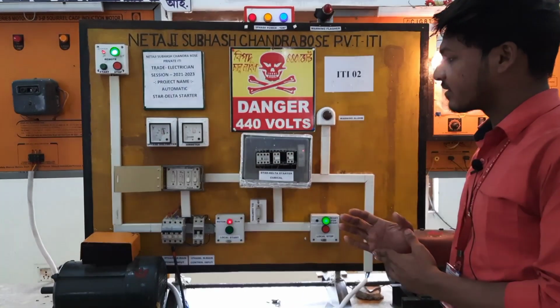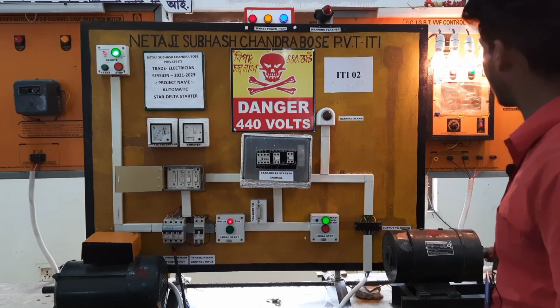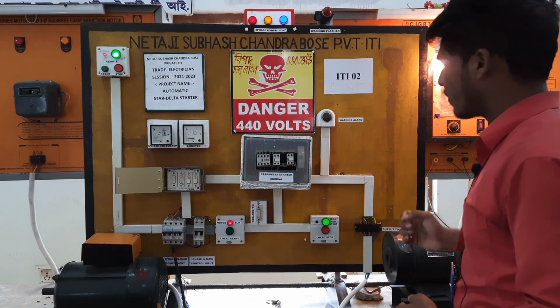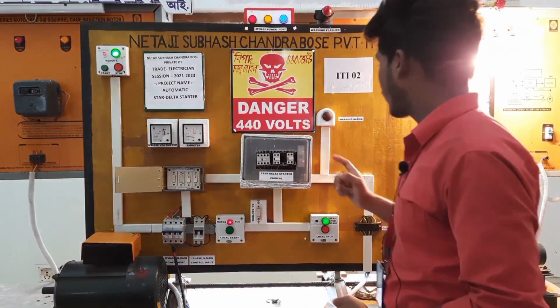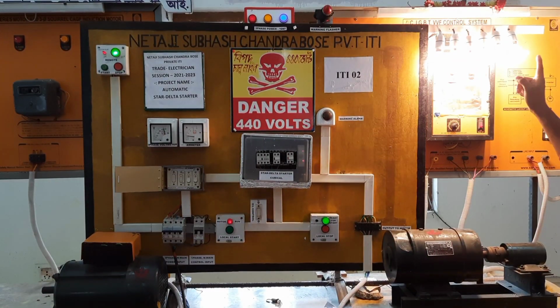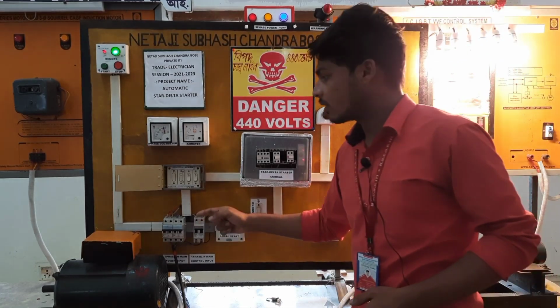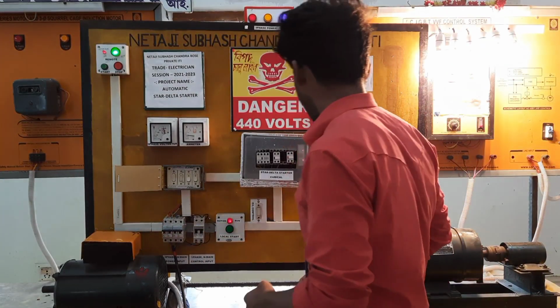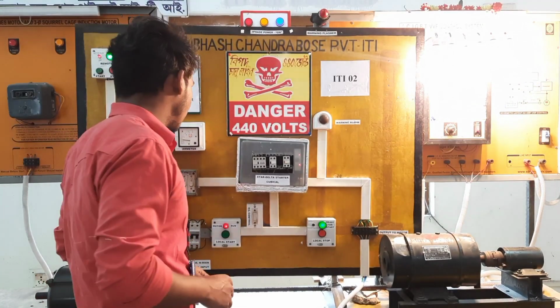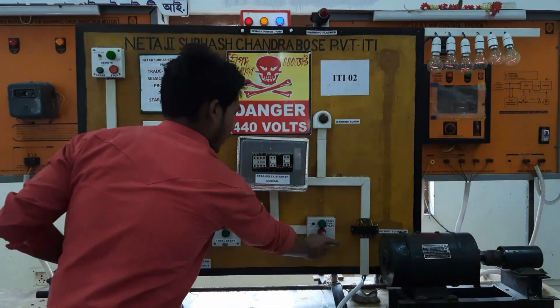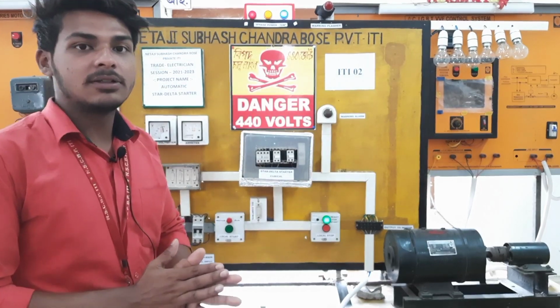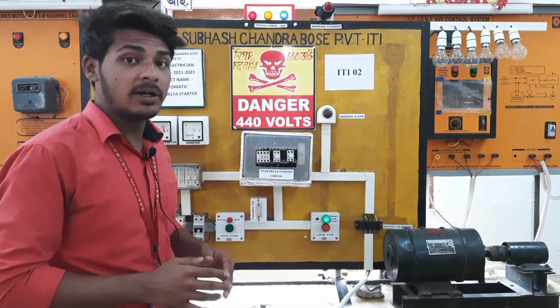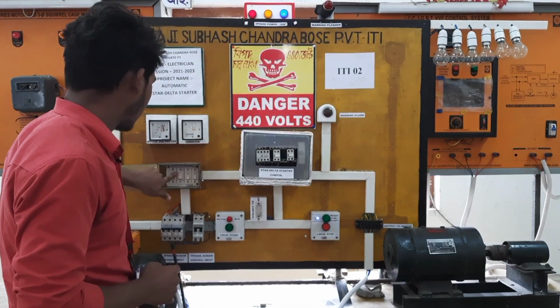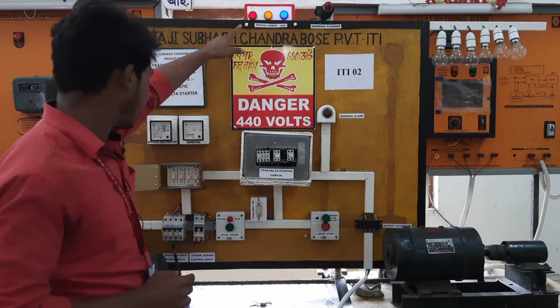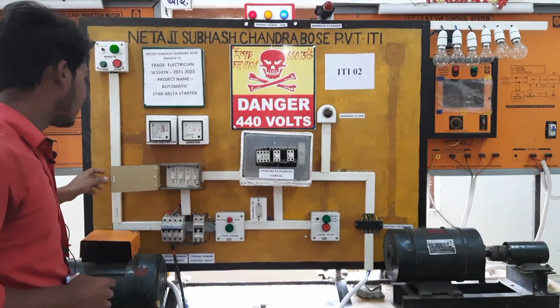Now start the motor. Now the motor coils become connected in star position and get low voltage. All the lamps glow dim. After 10 seconds at about 75% of rated speed, the motor coils become connected in delta and all the lamps glow at full voltage and the motor runs at normal speed. Now we can stop the motor both local and remote. With any kind of fault, that is overload, maintenance or control interlock position, the 3-phase power indication is on and 3-phase power is available here, but the motor cannot start.